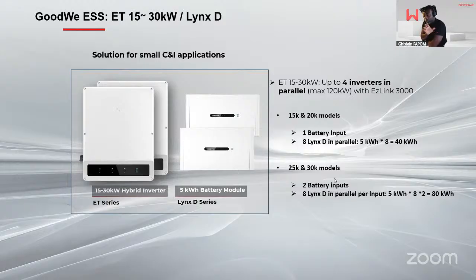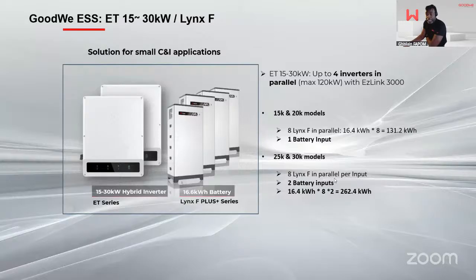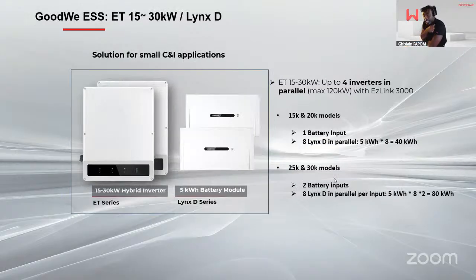And then there is the second battery series, which is the Lynx D, a newer generation of our battery. It offers less expandability, but more flexibility. With the Lynx F, you usually advise people not to upgrade the modules on the battery after a year, meaning if I build my tower of 3 or 4 batteries, I cannot add a module to the tower after a year because I will have an issue with SOH unbalances. With the Lynx D, I have a DC to DC converter included in each of the modules, allowing expandability at any time, really. You can have one module today and add other modules whenever you feel like doing it within the 10 years warranty of the batteries.